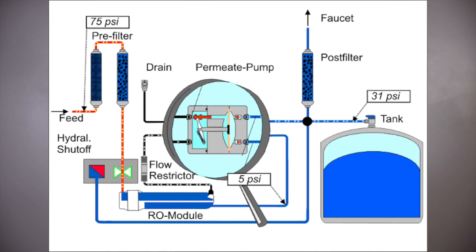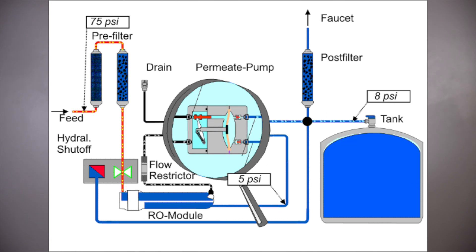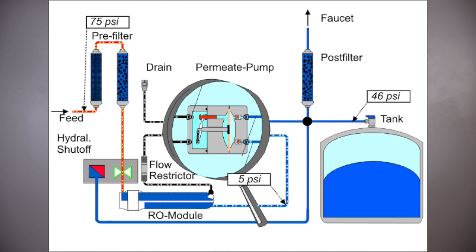The permeate pump acts as a motor to make these systems very efficient. It actually blocks the pressure buildup in the tank from getting back to the membrane, and it uses the water going to drain as the engine to push water into the tank, allowing the membrane to work at that recovery rate. The other benefit is the permeate pump provides quality of water all the way through. As the tank builds pressure, the quality of the membrane output goes down because it's fighting that pressure — but the permeate pump prevents that, so we have excellent efficiency.